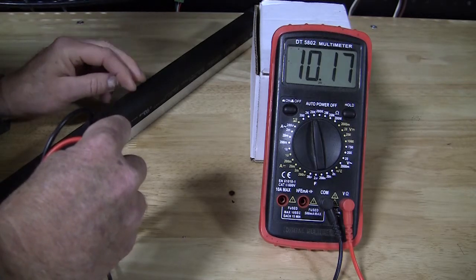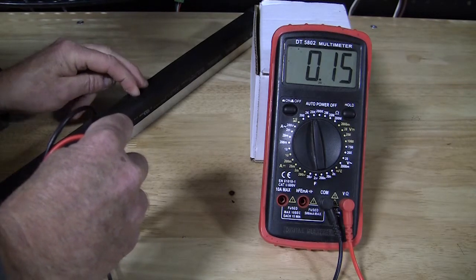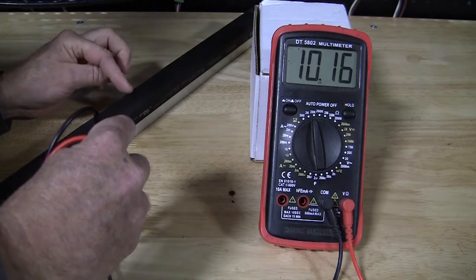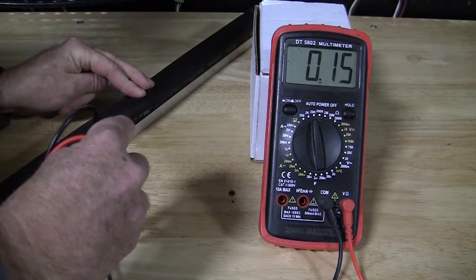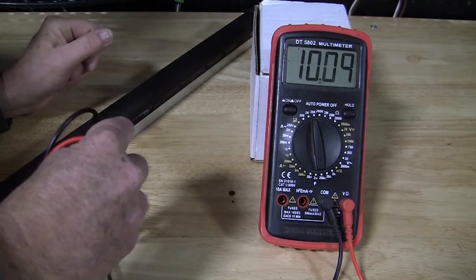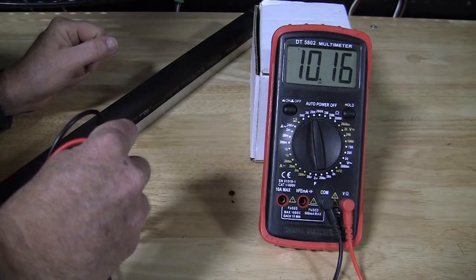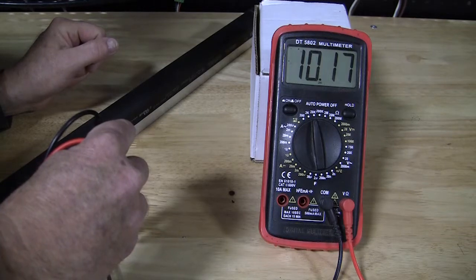So this is a resistive edge and this is how it works, it's just a conductive rubber material inside here. When something hits it the resistance changes and I'm going to show you how we can connect that to a 1050 board as a monitored entrapment device.